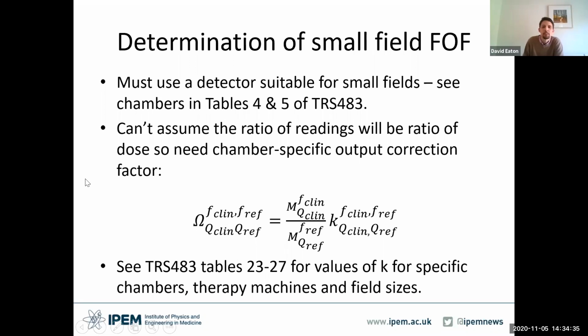And we also need to be careful about the type of chamber. There's guidance in different tables in the TRS report as to the minimum field size and correction factors to use for different chambers and different machines. We can no longer take the ratio of ionization to be the ratio of dose because of perturbation, lack of equilibrium, and possibly energy spectrum response differences. So we need correction factors to apply in these conditions.